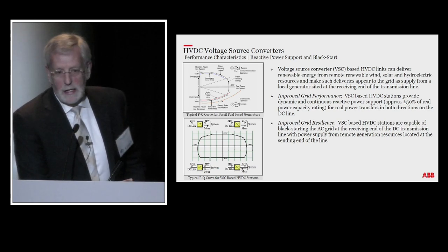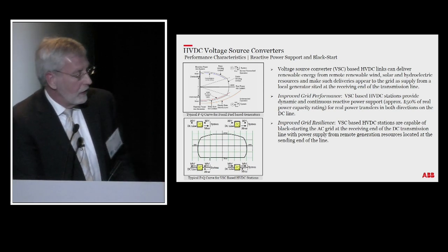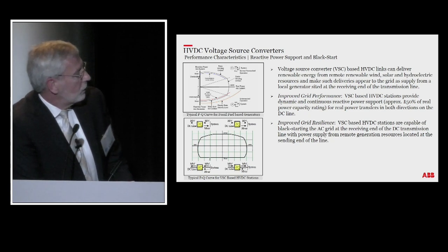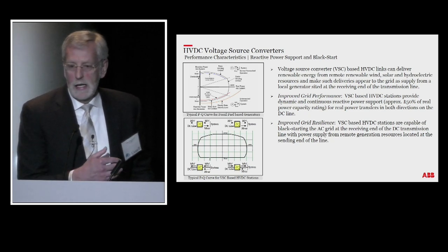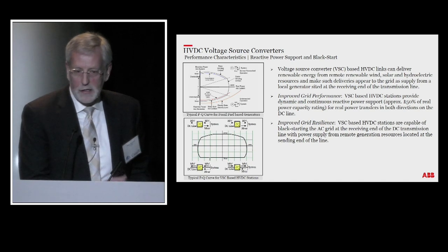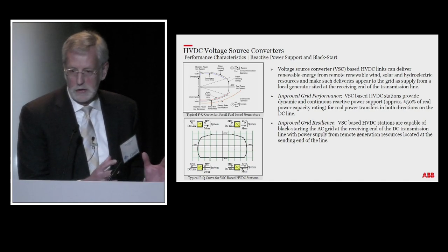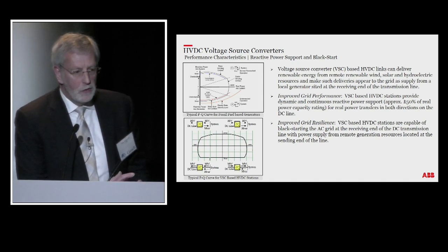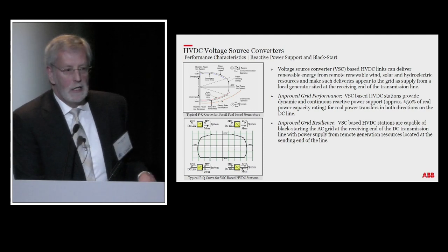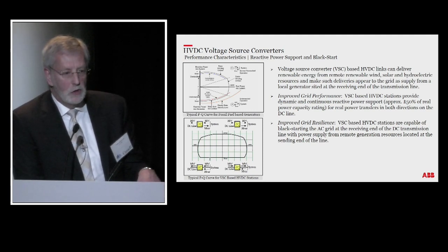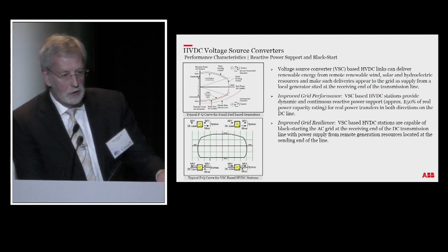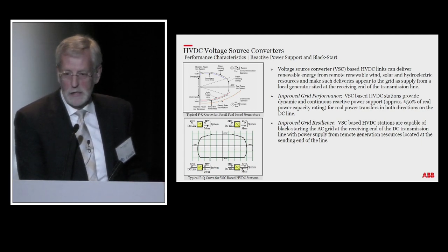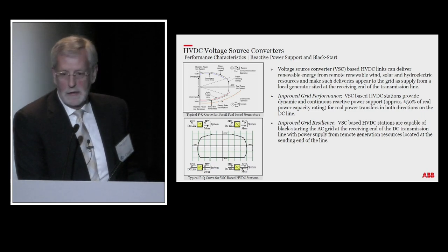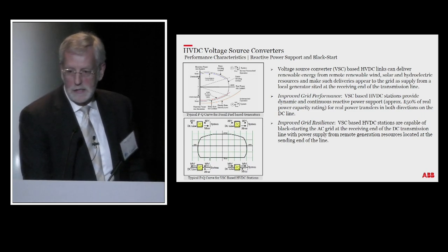If you have a 1,000 megawatt converter, you can supply 500 to 600 megavars of reactive power from it, and it's there both for continuous and dynamic support of the grid. Another characteristic of this new generation of converters is that you can actually use them for black starting a system, improving grid resiliency. If you have a blacked out area, you don't need any local generation there to black start it — you can black start it through the HVDC link and generation resources at the sending end.